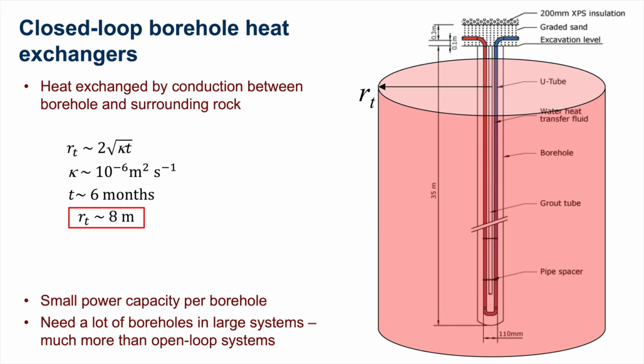It's dropped right down to 8 metres if we have a closed loop well. So what that means is we have a much smaller power capacity for each closed loop well, which basically means we need lots of wells to do closed loop. So open loop, we can use a small number of wells. Closed loop, we need lots and lots of wells to get sufficient heat or cool out of the ground.